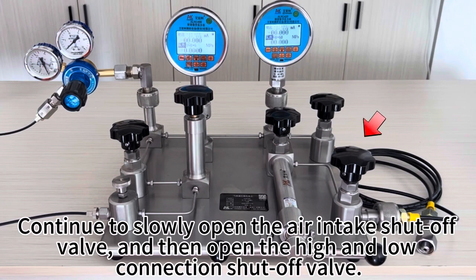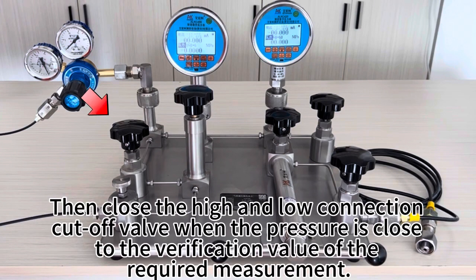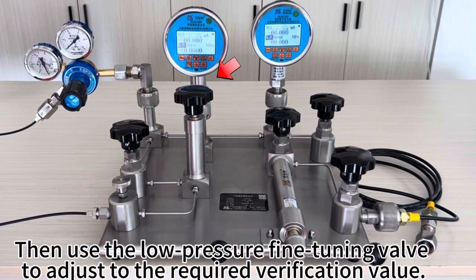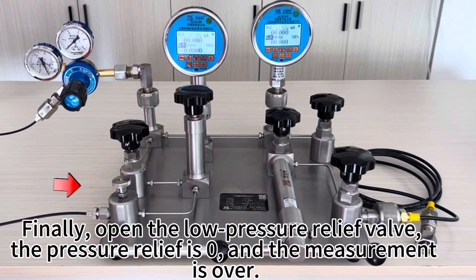Continue to slowly open the air intake shut-off valve, and then open the high and low connection shut-off valve. Then close the high and low connection cut-off valve when the pressure is close to the verification value of the required measurement. Then use the low pressure fine-tuning valve to adjust to the required verification value. Finally, open the low pressure relief valve. The pressure relief is 0, and the measurement is over.